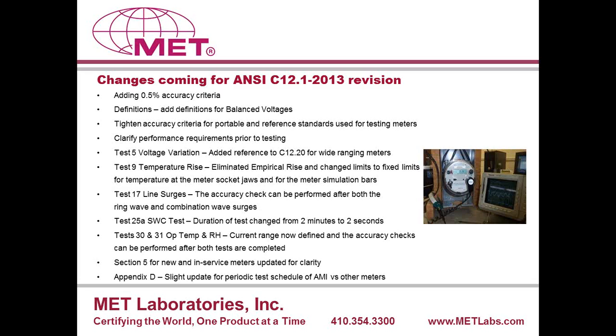Essentially, there's not a neutral reference to any of the circuits in the meter. So say for a Form 2S meter, you don't have that neutral reference in the meter. In the lab, you can test it and generally easily get compliance to the 0.5% accuracy criteria at C12.20, but realistically, when you deploy those meters in the field, there's certainly going to be imbalance between the A and C circuits, which would essentially add sometimes quite a bit of inaccuracy to that meter. So that's part of the reason for bringing that 0.5 criteria into 12.1, to address those non-Blondel configurations.